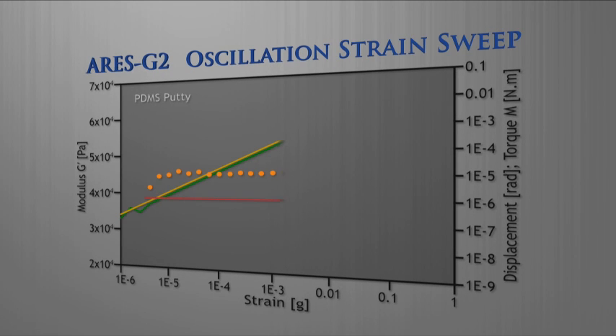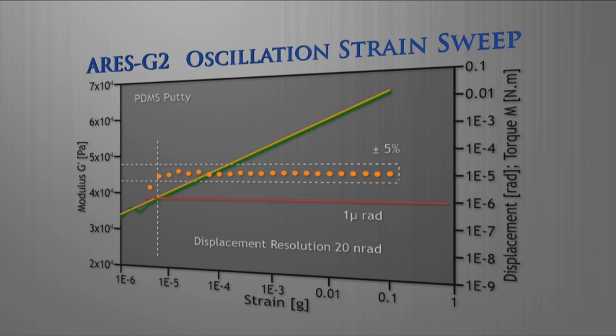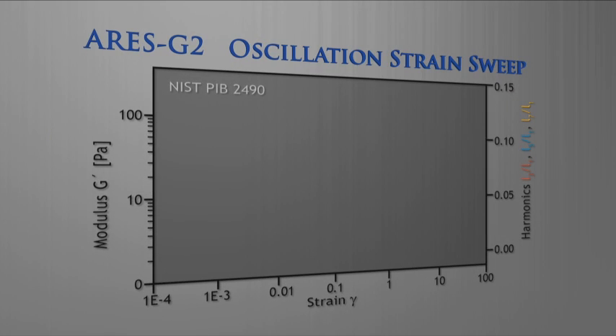The ARES G2 motor can control oscillatory strain levels down to one micro radian, allowing for classic linear viscoelastic analysis of materials with very delicate structures. Non-linear material behavior is observed as a decrease in G prime in the strain sweep.